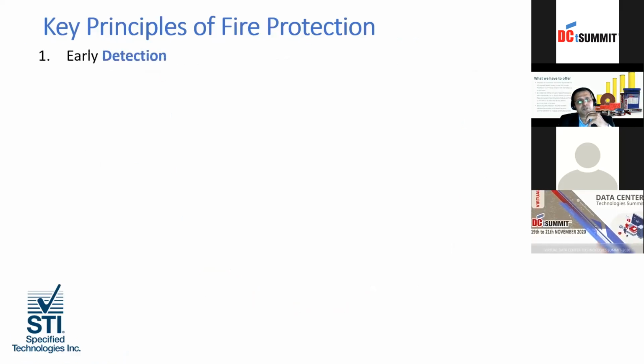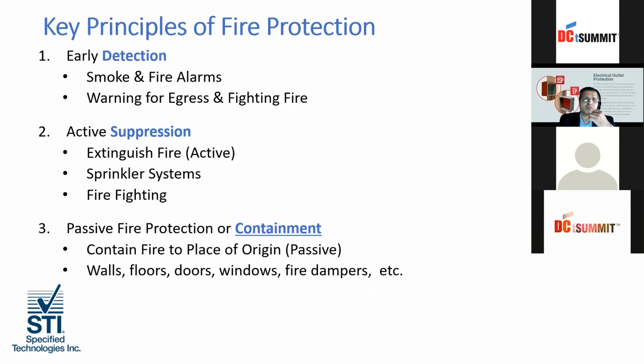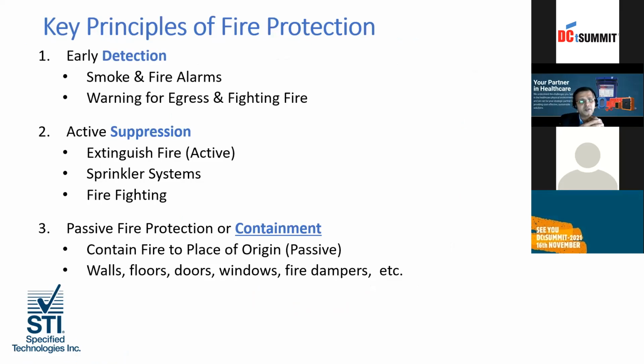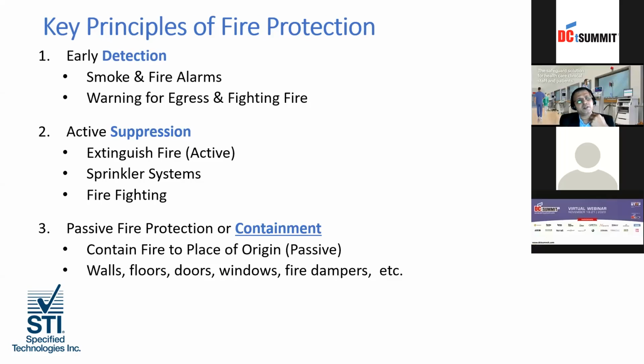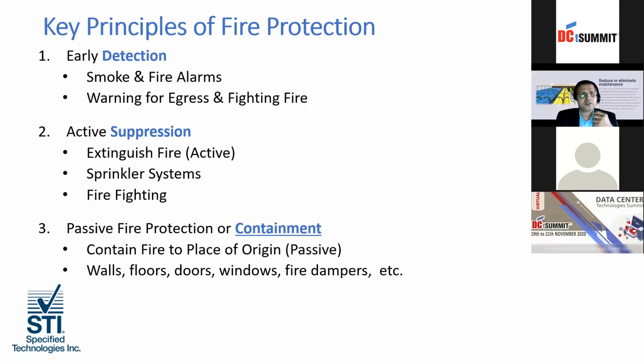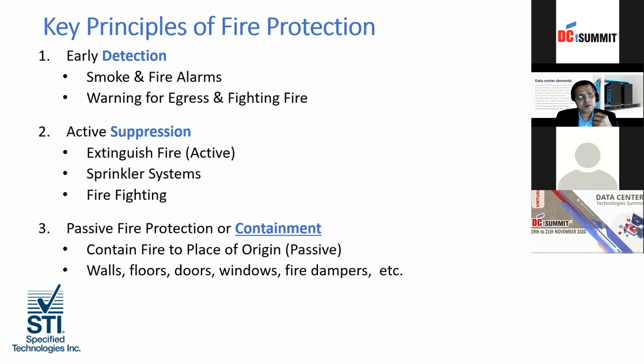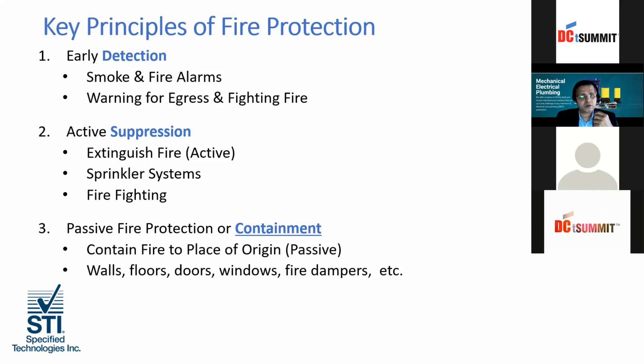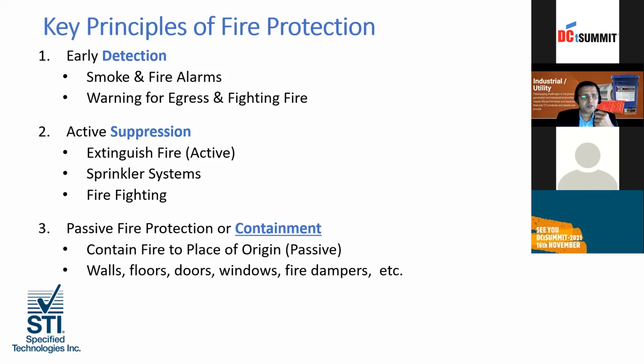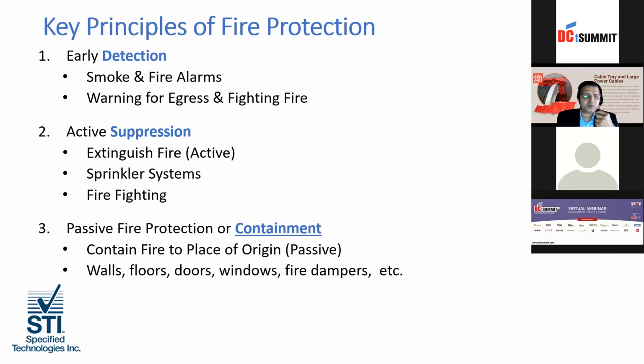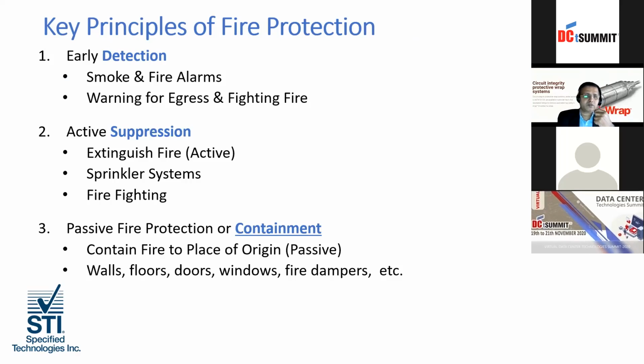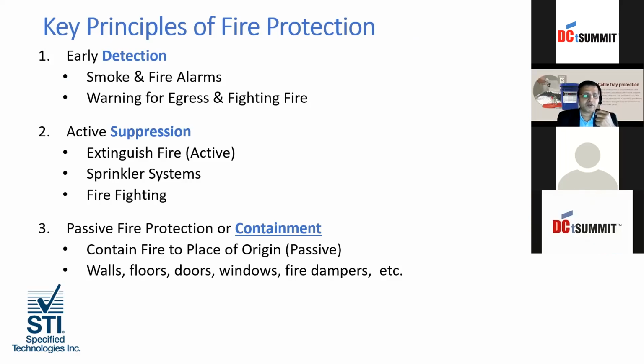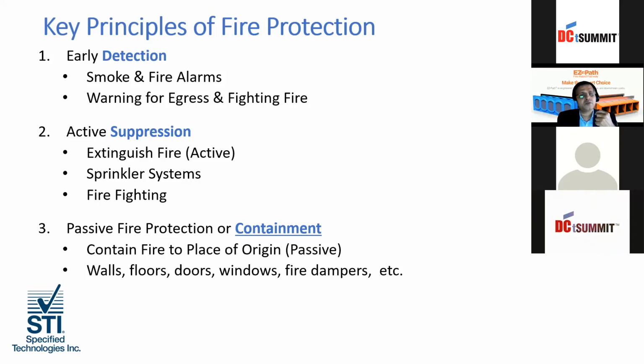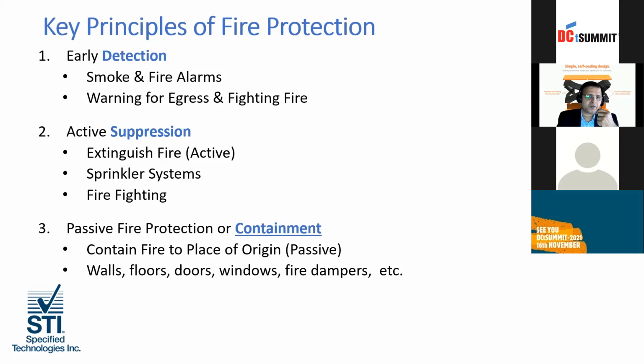Key principles of fire protection: we have early detection, smoke and fire alarms. Active, we have sprinkler systems and firefighting. And the third is the passive, the passive fire protection systems or the containment. So all these are key and important. Early detection is most important. In case of fire, the fire alarm should buzz so that the people can be evacuated. We have active suppression systems like the sprinkler systems, firefighting systems, extinguishing systems. And passive fire systems: wherever there are through penetrations for a fire-rated wall or a floor, those areas have to be sealed with an equivalent amount of fire-rated systems.